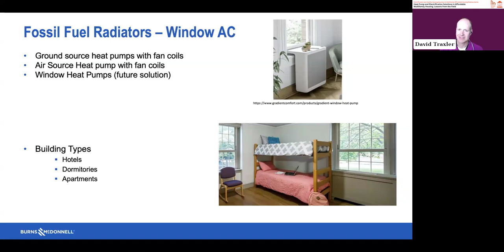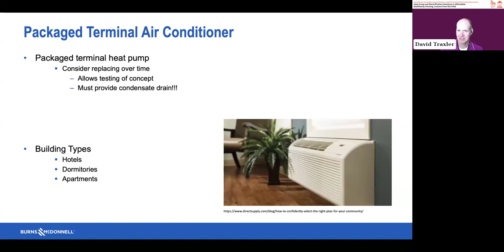The next one is packaged terminal air conditioners. They are developing, and have available, packaged terminal air conditioners that are heat pumps and work in colder climates, so if you have one of these, you could try one today. You have to be mindful these require a condensate drain, whether you drain through the exterior wall or down through the building, it's different than your traditional packaged terminal air conditioner, which did not require a drain.